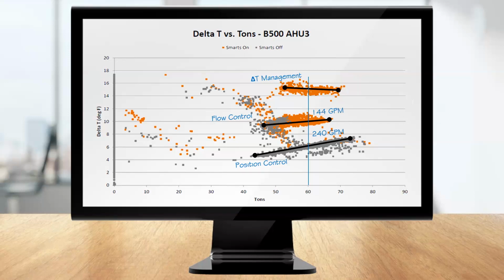In flow control, we utilized 144 GPM. And you'll notice that our delta T increased from 6 to 10. When we put that valve into delta T management, we went to 96 GPM and we achieved the design of 15 degrees delta T to achieve that same 60-ton load. If you look at that, 96 GPM is a 60% reduction in the position control flow rate of 240 GPM to achieve that same load, which is a massive increase in efficiency.